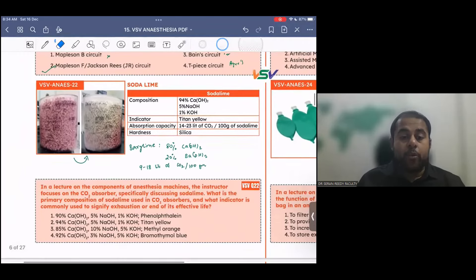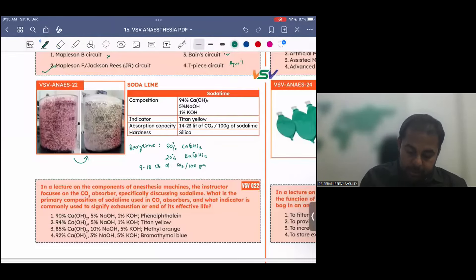In a lecture on the components of anesthesia machines, the instructor focuses on the carbon dioxide absorber, specifically discussing soda lime. What is the primary composition of soda lime used in carbon dioxide absorbers, and what indicator is commonly used to signify the exhaustion of its effective life? 90% calcium hydroxide, 5% NaOH, 1% KOH, and phenolphthalein indicator, you answered it correctly. It is 94% calcium hydroxide, 5% NaOH, and 1% KOH, and the indicator is Titan yellow.